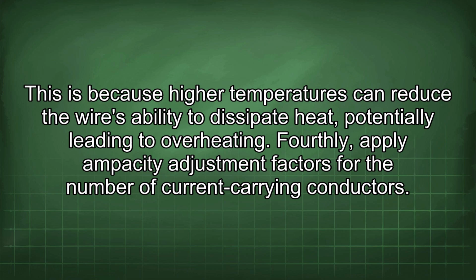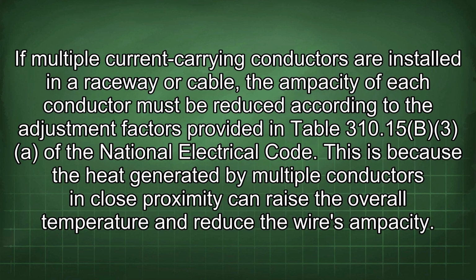Fourthly, apply ampacity adjustment factors for the number of current-carrying conductors. If multiple current-carrying conductors are installed in a raceway or cable, the ampacity of each conductor must be reduced according to the adjustment factors provided in Table 310.15(B)(3)(a) of the National Electrical Code. This is because the heat generated by multiple conductors in close proximity can raise the overall temperature and reduce the wire's ampacity.